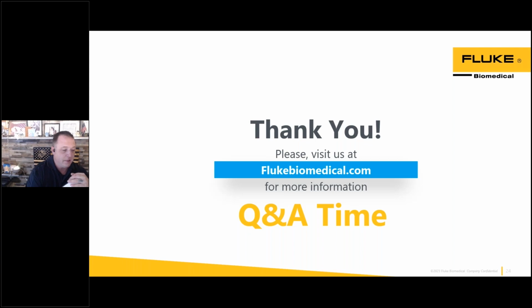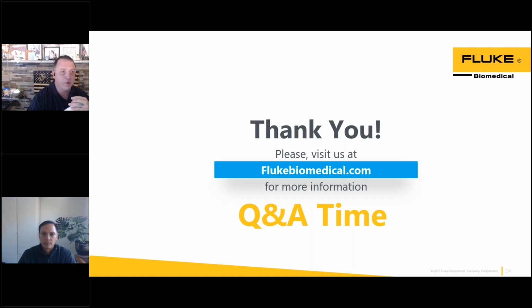No, actually it doesn't. Once you prime the channel one time, because it's using that piston-driven stepper motor, you don't have to worry about losing that prime. So after you prime it one time, you can go right into the next flow test. Now for the Alaris folks, it's built into the procedure to do a 30-second or 5 milliliter prime. Just let it run, and then you start the test once it completes that. So you don't have to alter that software, just let it run. Just run right through the IDA-6. When you get ready to run the actual measurement, push play and off you go.